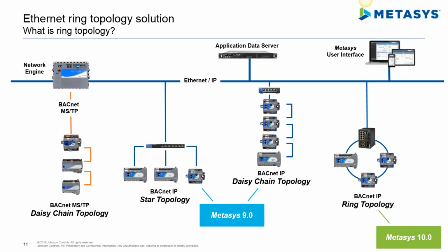Ring topology provides a happy medium between your installed cost and network resiliency. Ring doesn't require as many ports on the switch or as much Cat6 Ethernet cabling as star topology, but it also provides the resiliency in case a cable breaks or if a controller goes offline, because with the ring topology, there are two pathways to each controller. And the redundancy of the MRP system will allow the communication to occur in the event that one node might fail.